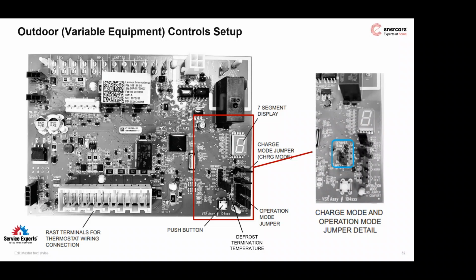We want to make sure that when there is a defrost sequence, the defrost is run long enough and hot enough to completely clear the outside of the coil. 50 is too low. Maybe in Florida 50 would work, but if we're going to operate heat pumps in our Canadian climate, 70 as a minimum, 90 preferred. Please make sure those are set up.